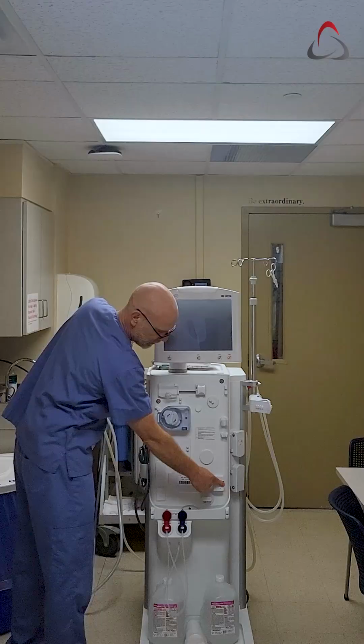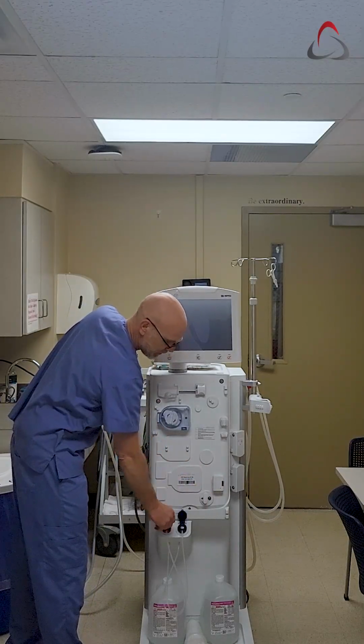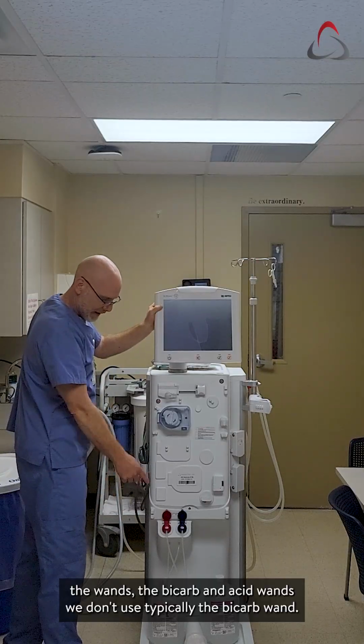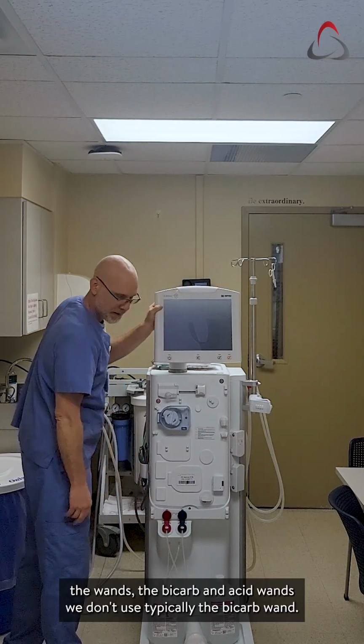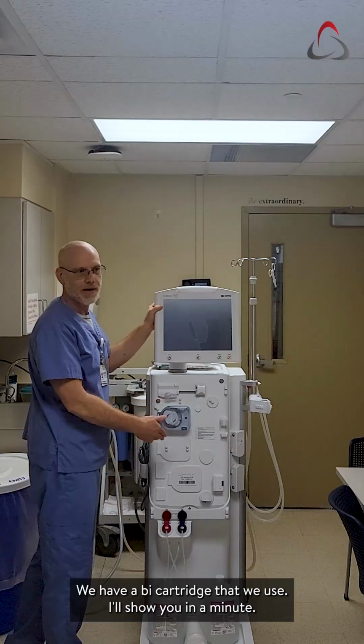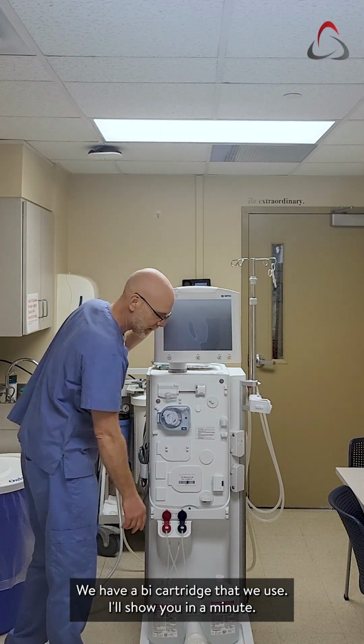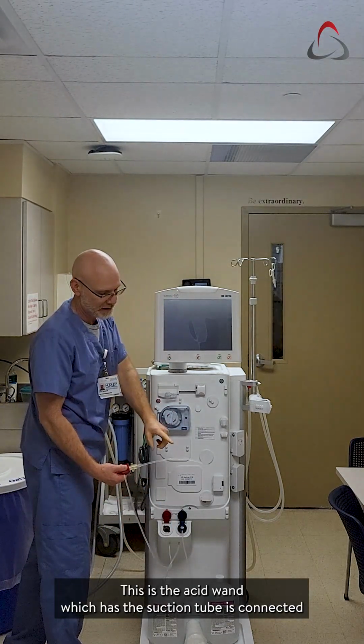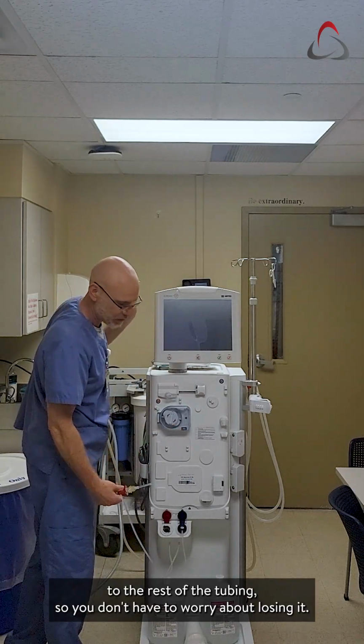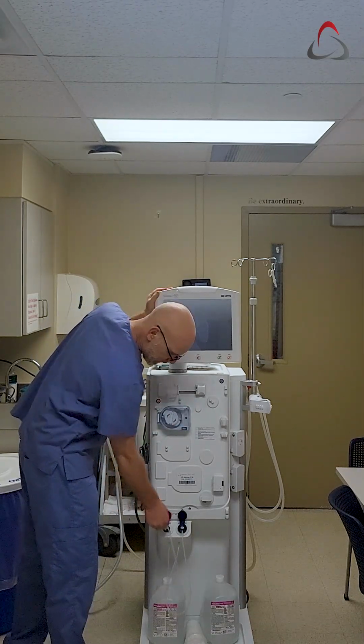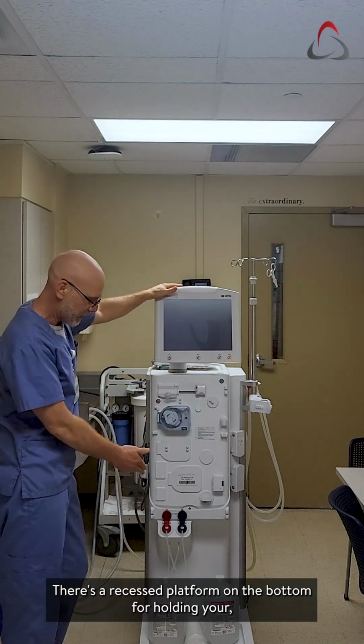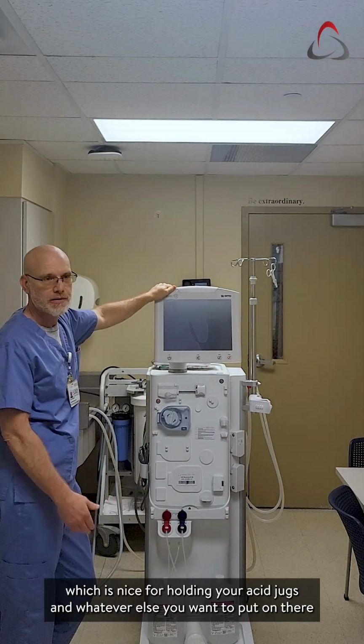The air detector and blood detector. Waste port. The wands, the bicarb and acid wands. We don't typically use the bicarb wand. We have a bicartridge that we use. I'll show you in a minute. This is the acid wand, which has the suction tube connected to the rest of the tubing, so you don't have to worry about losing it. There's a recessed platform on the bottom which is nice for holding your acid jugs and whatever else you want to put on there, so you don't have to worry about it rolling off on the floor.